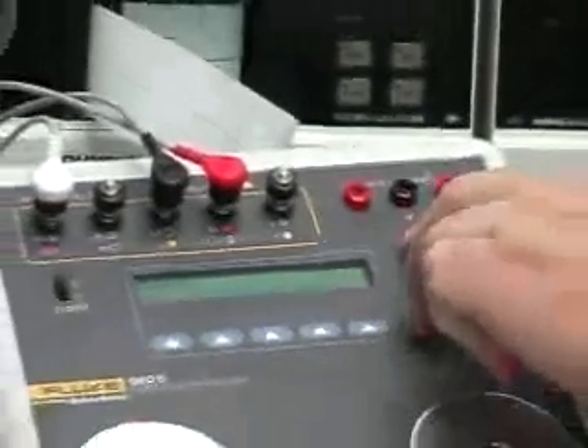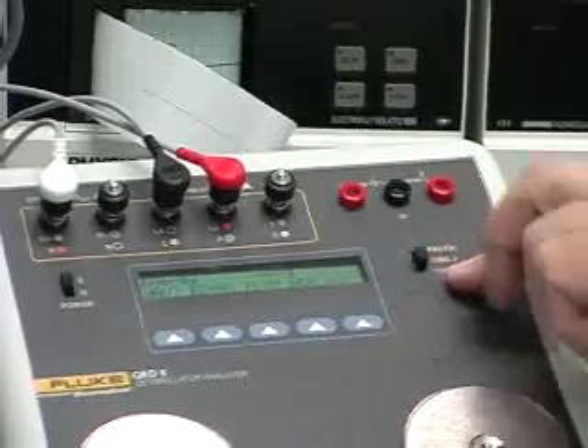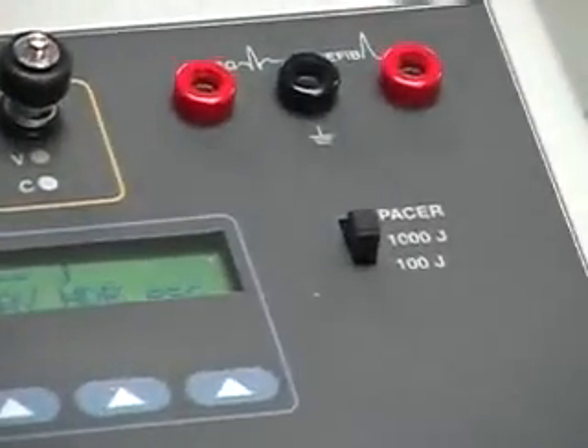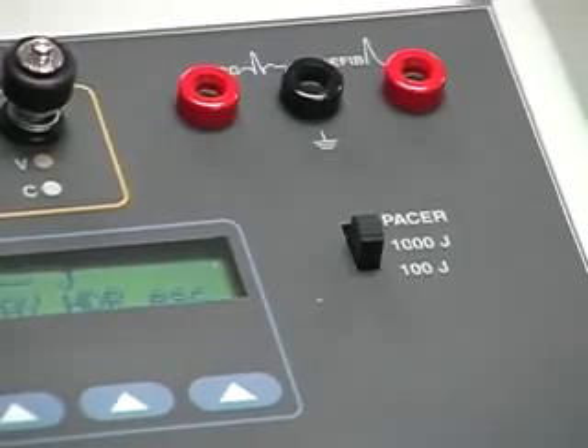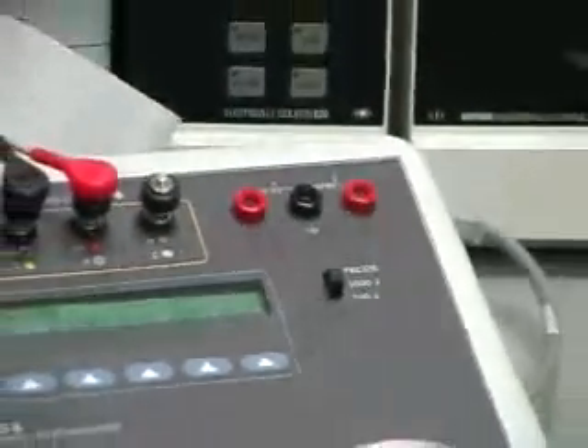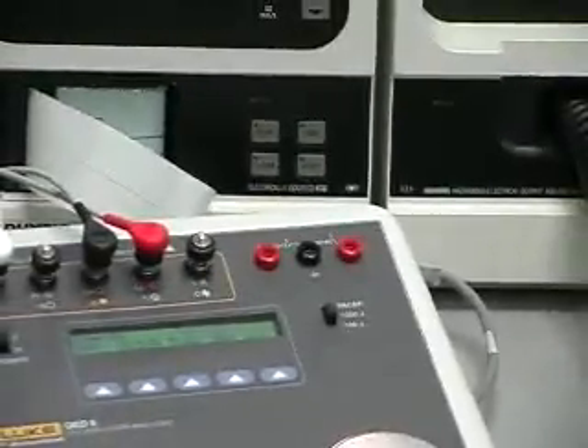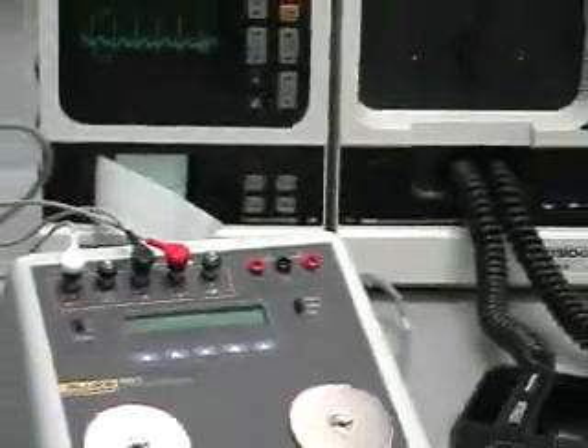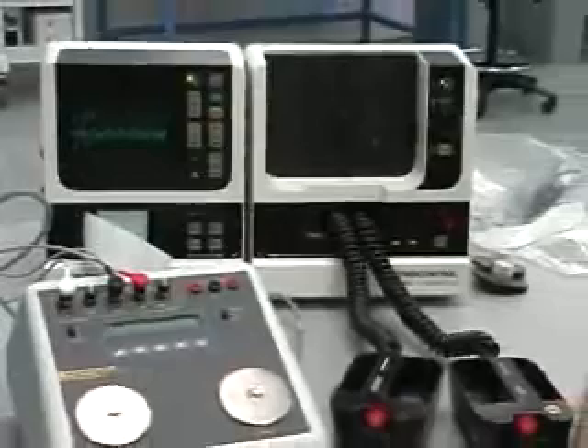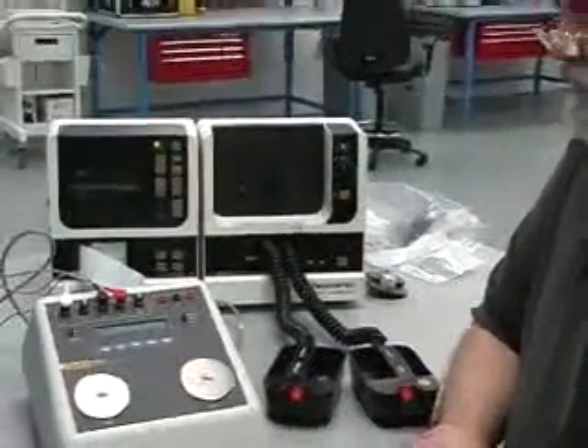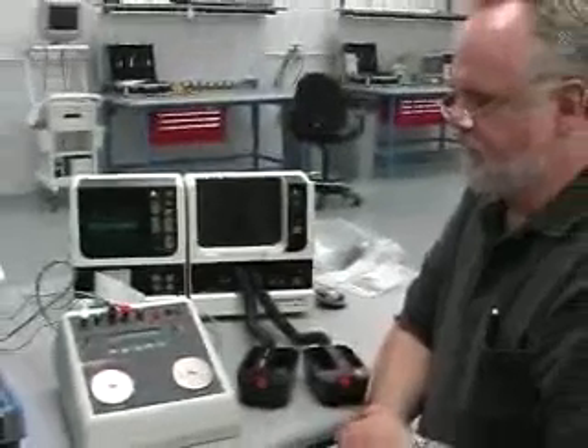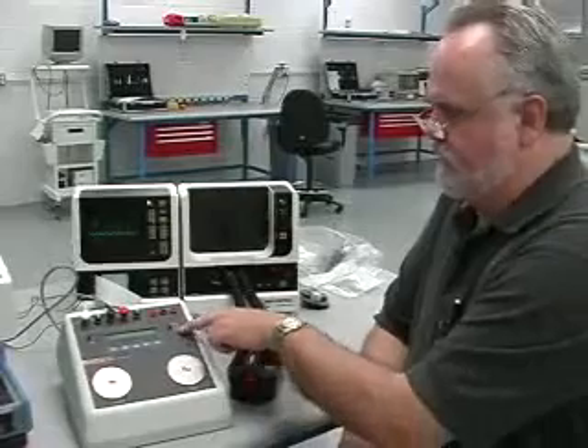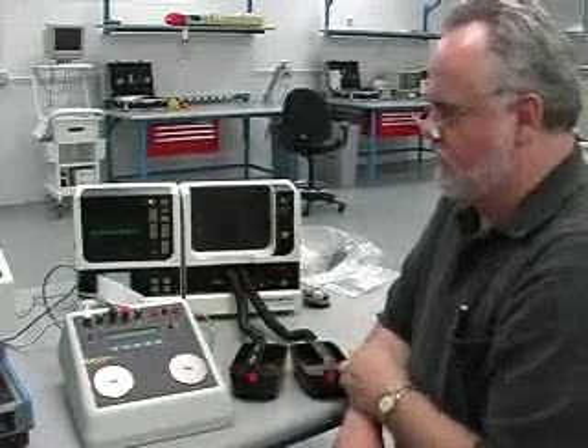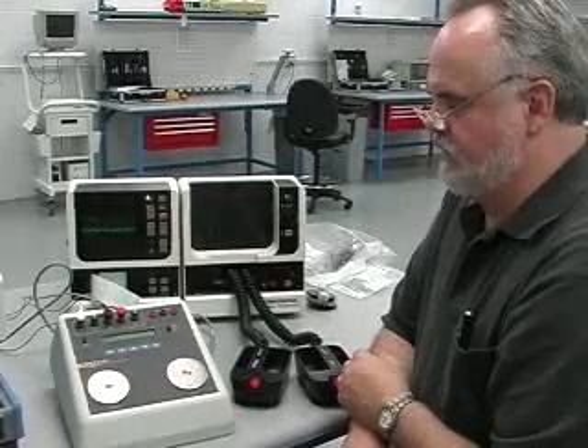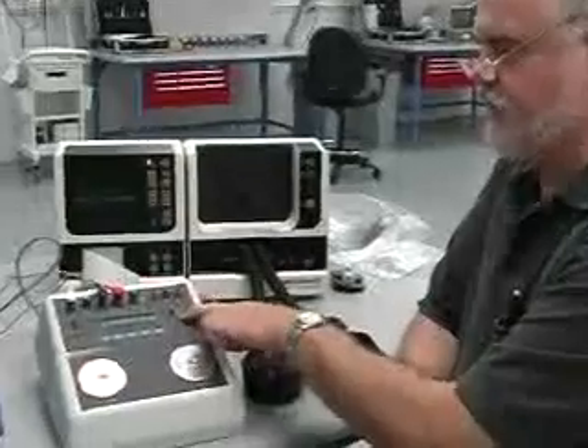Okay, so we're going to go first at lower defib energies, values under 100 joules. Again, you're not going to damage the analyzer if you have it in the lower range and hit it with 360 joules. The same high voltage attenuator is always in the circuit. It will simply overrange and display an overrange on the LCD readout. But you will also get a more accurate reading if you're measuring low energies if you go to the 100 joule position of the switch. So we're going to start off on the basics, a lower energy test, leaving it on the 100 joule range.